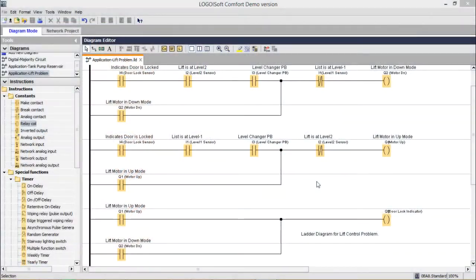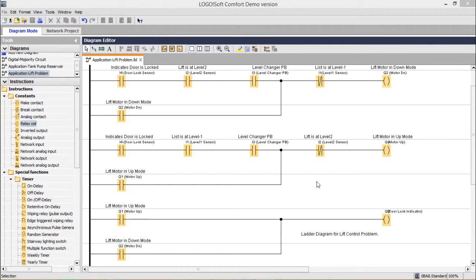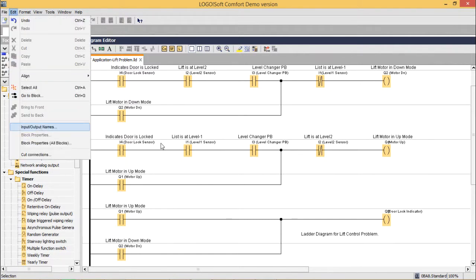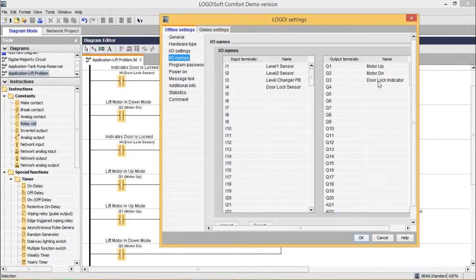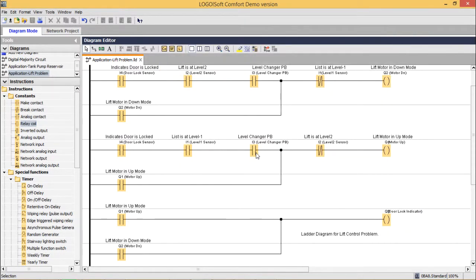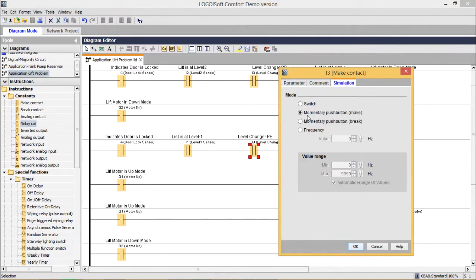In this session we are discussing the ladder diagram of the lift control problem. The input/output names are: I1 = level one sensor, I2 = level two sensor, I3 = level changer push button, I4 = door lock sensor. Q1 = motor up, Q2 = motor down, Q3 = door lock indicator. I1, I2, and I4 are sensors acting as switches, while I3 is configured as a momentary make push button.